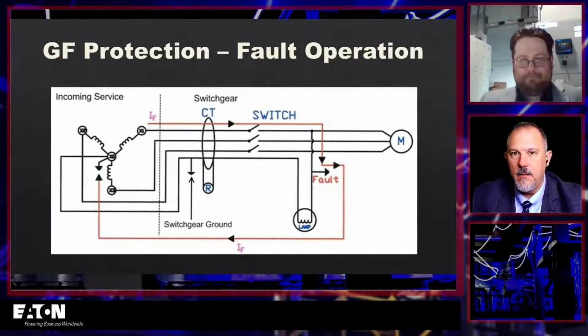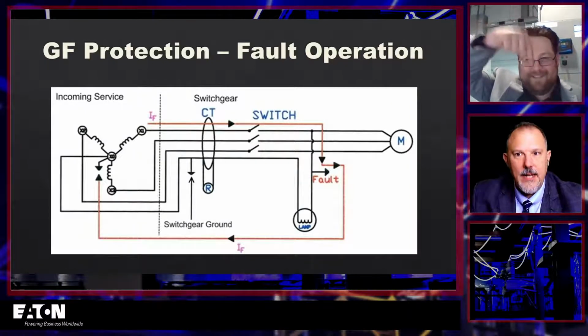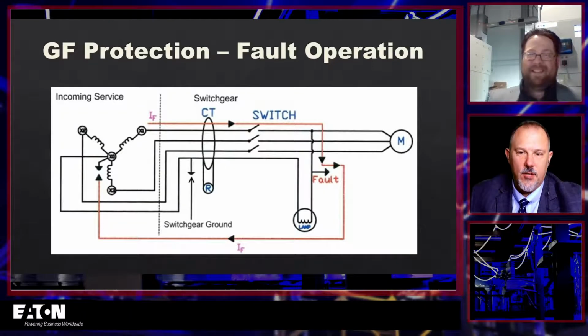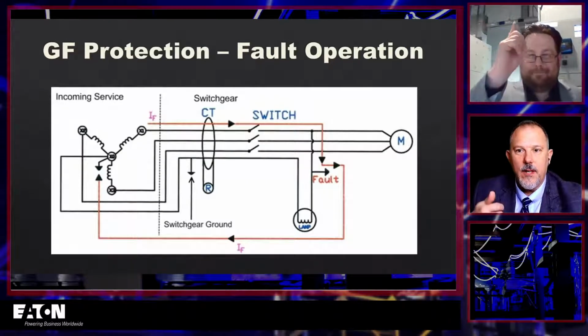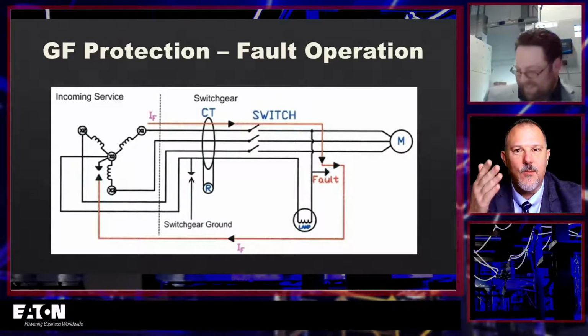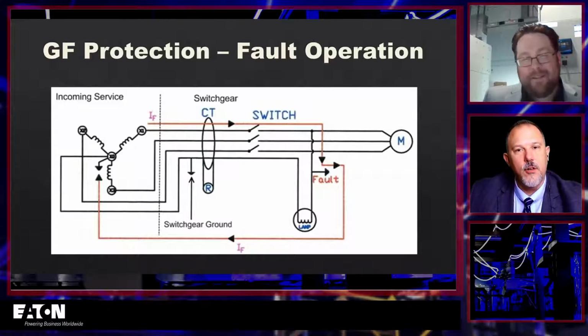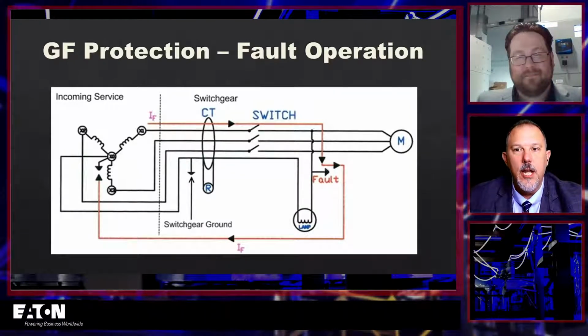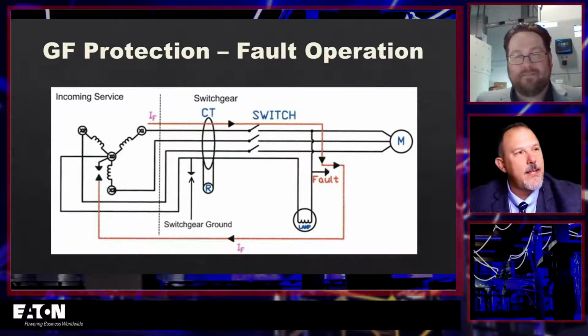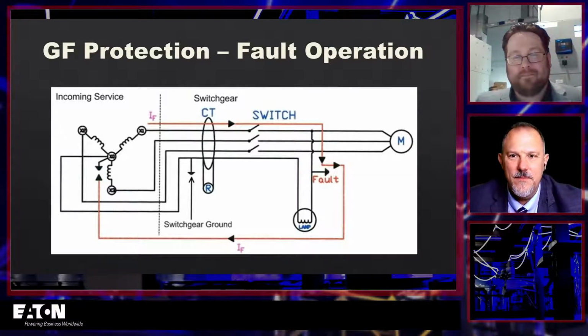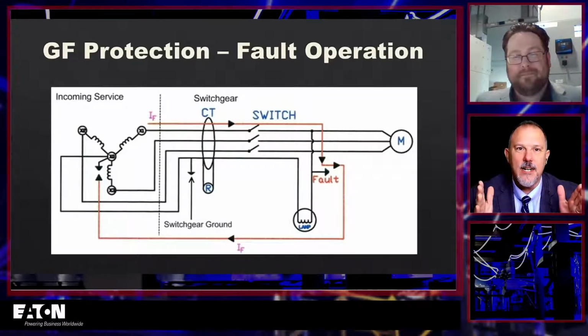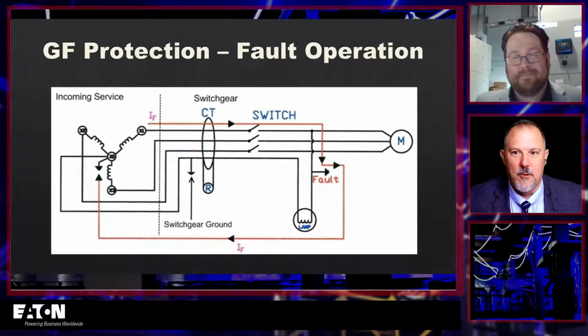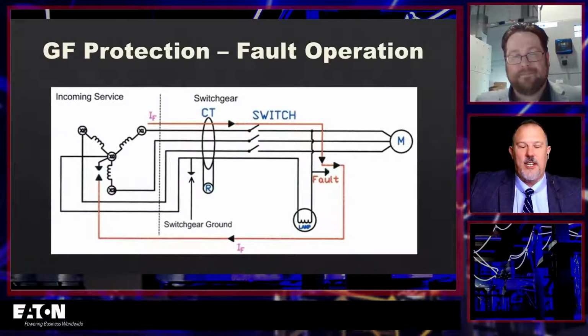I said, "The impedance will go down." Right. He goes, "And what happens to the fault current?" I says, "Yeah, well, it will go up." He says, "That's why you have more fault current going through the equipment grounding conductor, and you need to make sure you protect it." I'm like, but if I shorten the conductor, I can get more current to flow through it than a long run where I'm just changing the size.